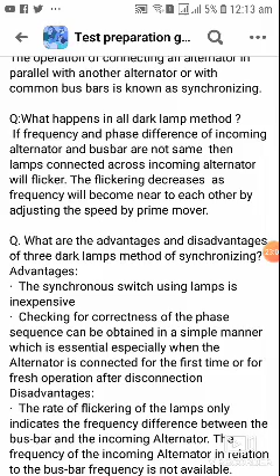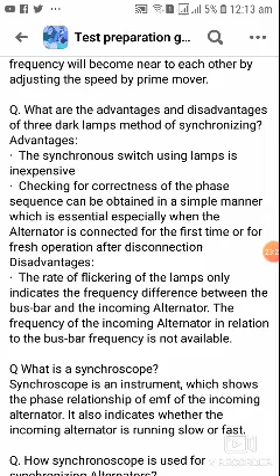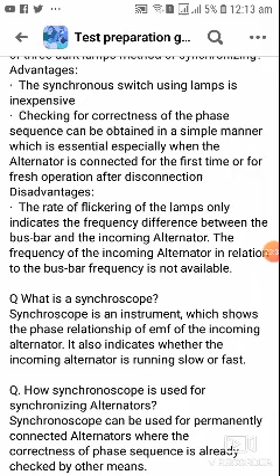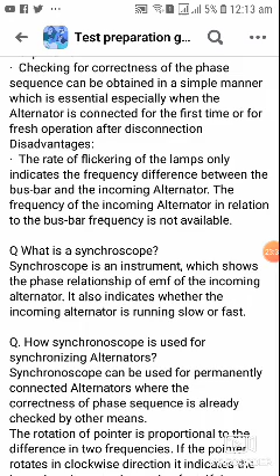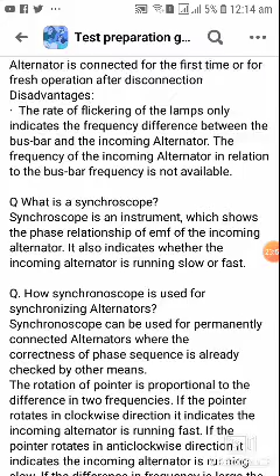Question number 43. What are the advantages and disadvantages of three dark lamp method of synchronizing? Advantages. The synchronous switching using lamps is inexpensive. Checking for correctness of the phase sequence can easily be obtained in a simple manner, which is essential especially when the alternator is connected for the first time or for fresh operation and disconnection. Disadvantages. The rate of flickering of the lamps only indicates the frequency difference between the bus bar and incoming alternator. The frequency of the incoming alternator in relation to the bus bar frequency is not available.